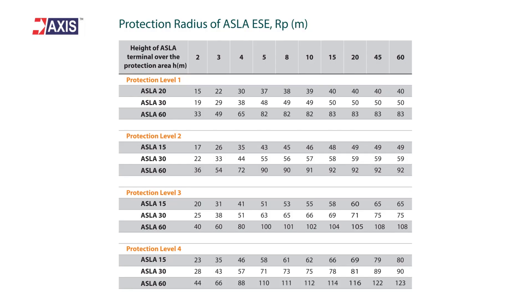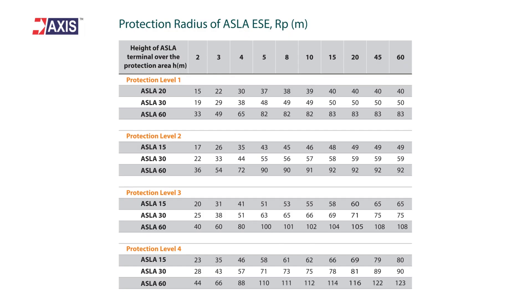We have done all the hard work of calculating this formula for various configurations so that you don't have to. Just refer to this table to know the radius of protection for your structure. Now let's use the same values as the example above using this table. Let's say the height of your ESE arrester is 5 meters, you are aiming for a protection level of 4 for the ASLA 60 model, and using the table again, you get the coverage area as 110 meters.